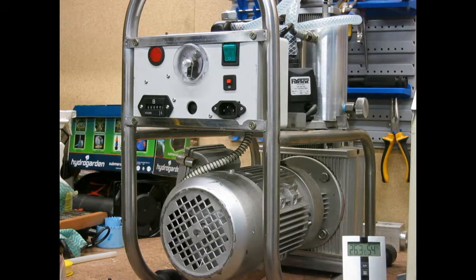That unit is based on the same platform as Omega Raptor. The only difference is that we don't like the automation control of Omega Raptor and we don't like their filter, because I reckon that their filter is too small. Also it's filled with silica beads, so it's not an efficient way of filtering moisture, simply because once those silica beads are contaminated with water, they have to be treated, and there's no way of treating those silica beads because it's too hard to open that filter.